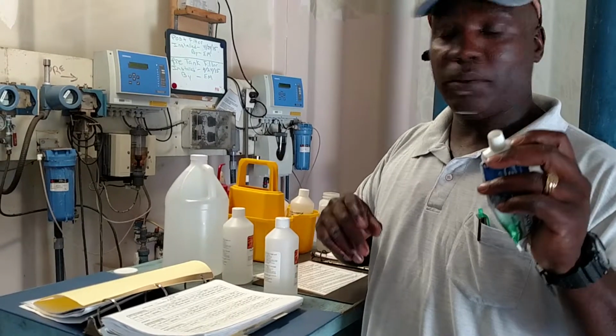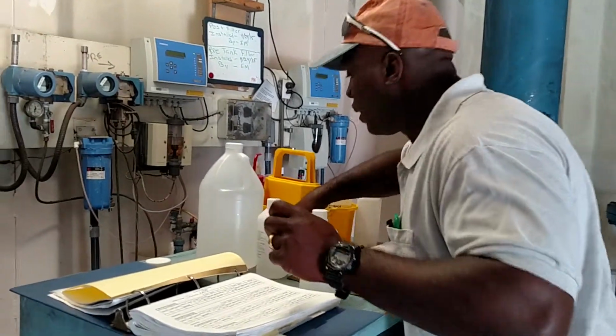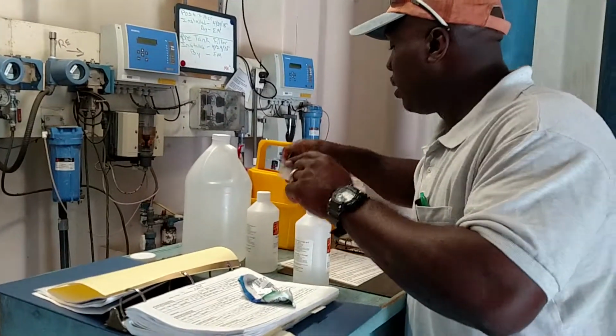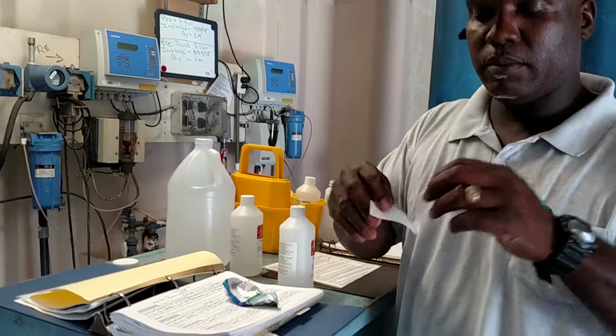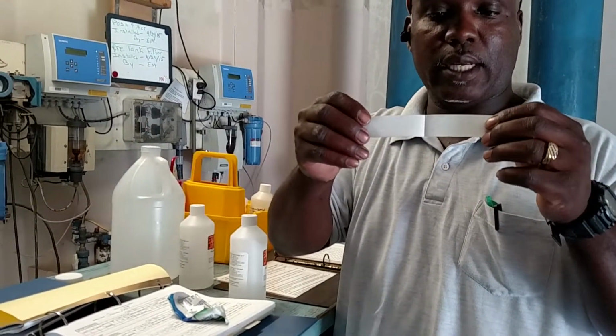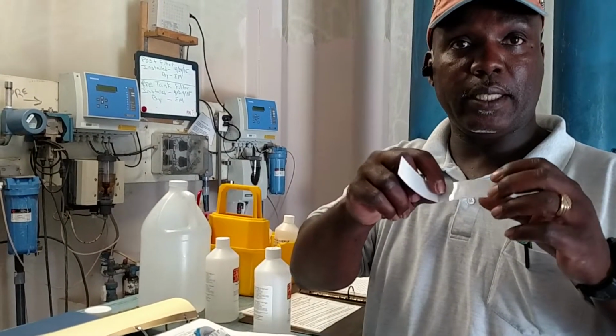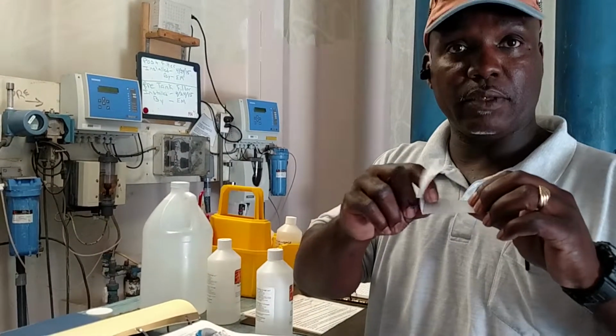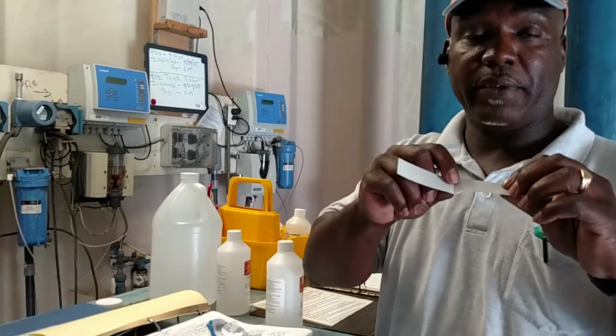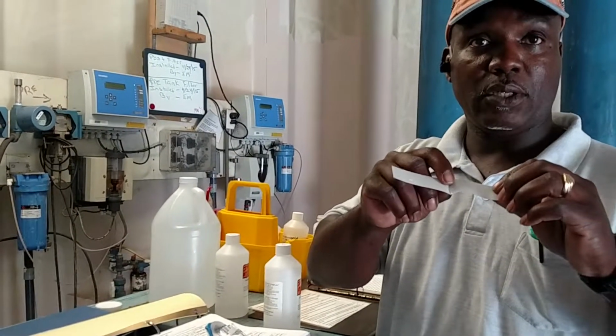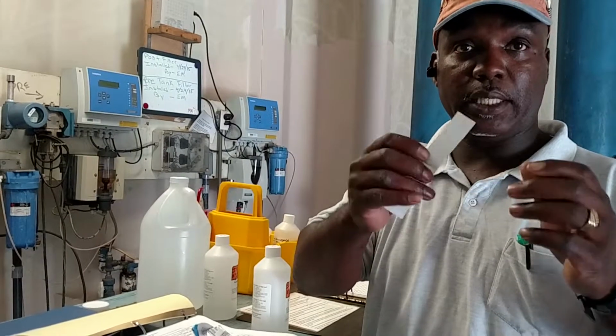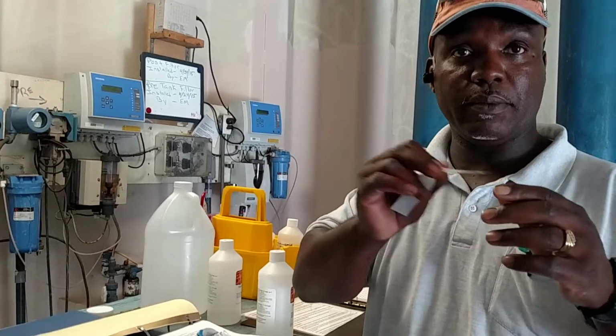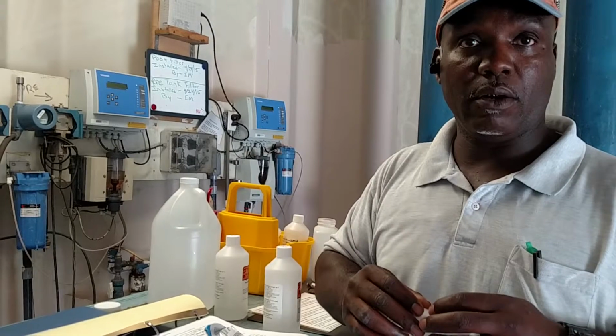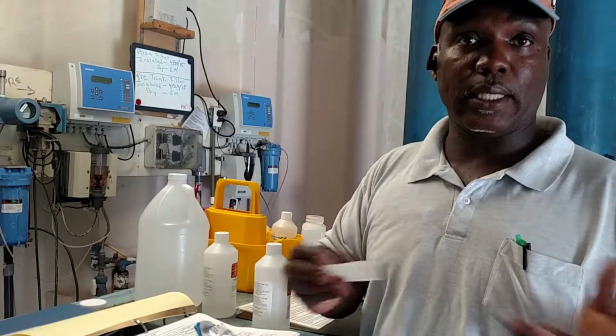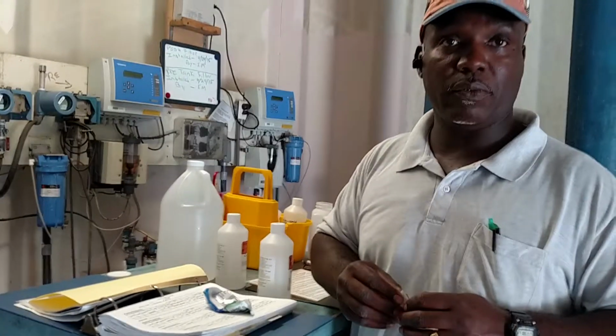What I found out, what they were saying, is that all the probes come with a little, basically like a little sandpaper. And you just put a little dab of toothpaste on there, and then you're supposed to put it on a flat surface and rub on it. I haven't found that to be successful. So what I normally do is put a little bit on here and just gently rub over the surface of it and then rinse it off. And normally once I do that, sometimes it can take up to 24 hours for it to stabilize.